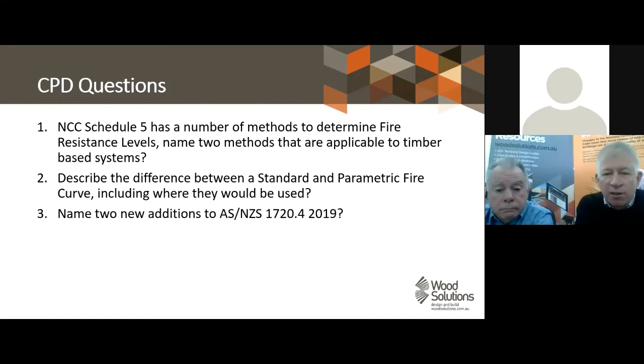So just scrolling down with some more questions, another one for you. This is one from Anthony. Can you please elaborate more on what assessment means in addition to the accredited standard fire tests? Under the NCC, if you were to develop a performance solution, then the NCC requires you to demonstrate that the performance solution has been assessed in accordance with one of the assessment methods listed in the NCC.